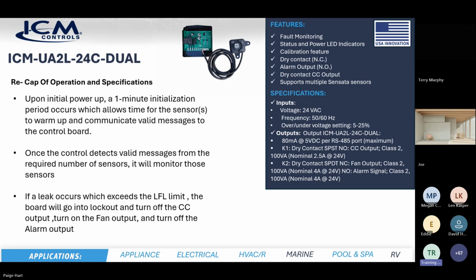If the control detects a valid leak that exceeds what they call the low flammability limit, the board will go into a lockout, turn off the compressor contactor output, turn on the fan output, and turn off the alarm output. Now, that's going to throw everybody for a loop. It works sort of reverse of what you would think.